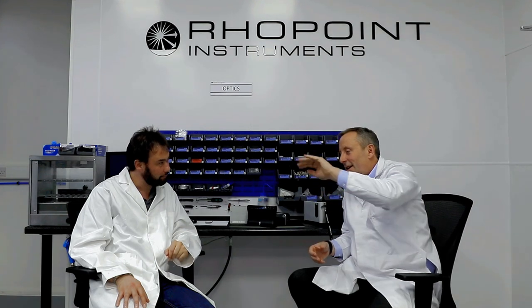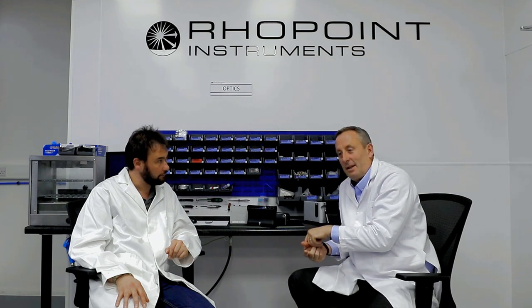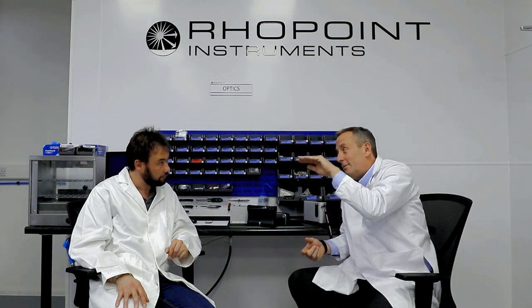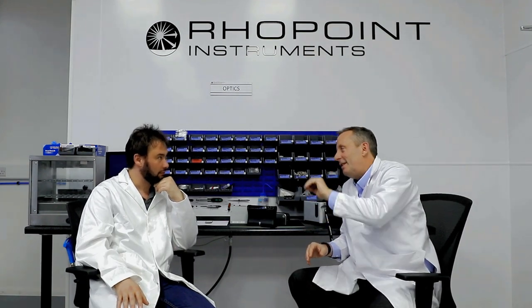The other thing which we're working on is, when we're building a car, there's several layers which go into the final appearance. So we have the substrate, the steel and the aluminium, then we have the e-coat, the fillers, then the base coat, and then the clear coat. This instrument can actually measure at all the levels. So we can measure the steel, the e-coat, and all those things. So that's helping us to understand at the OEM level how the final appearances are.